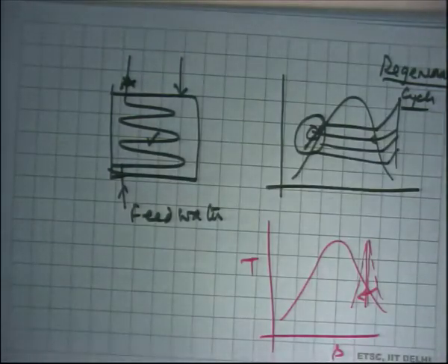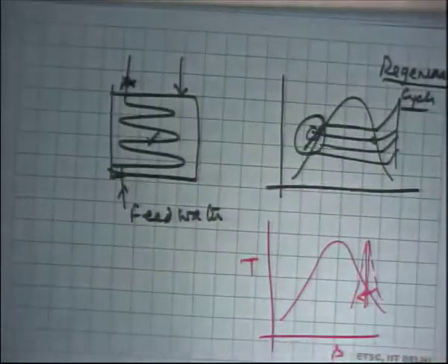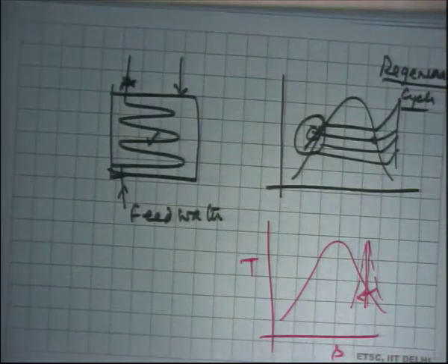So, you normally have a certain number of feed water heaters which you use depending on the maximum temperature of the cycle. Okay, depending on the temperature at which the steam enters the turbine, or depending on the pressure at which the steam enters the turbine, the number of feed water heaters vary. Okay. In most of the subcritical power plants of the kind that we saw there, the boiler that we saw was subcritical because the pressure of the boiler is less than the critical pressure of water. Critical pressure of water is about 220 atmospheres. The pressure of the boiler that we saw is something like 190 bar, right.